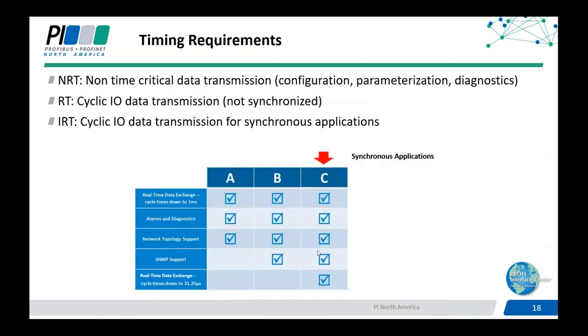Relating those conformance classes to timing requirements: conformance classes A, B, and C are all able to use the non-real-time channel and the real-time channel, which are the standard communication channels for PROFINET. But only conformance class C devices can communicate through the IRT channel, because they have that synchronous application. So if you require that capability, you have to look for conformance class C devices.